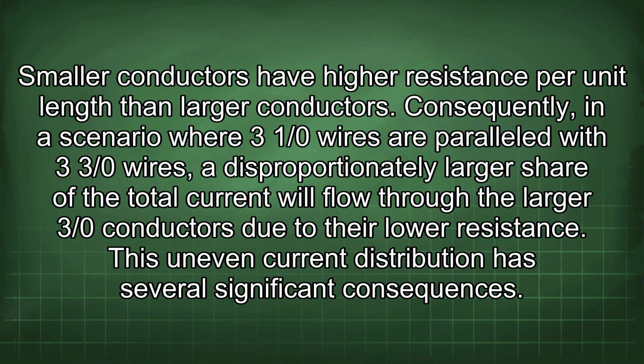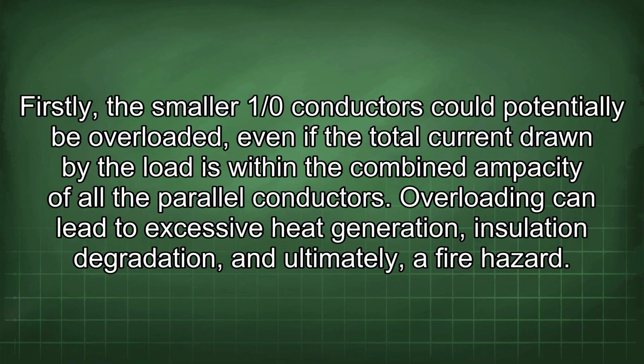Consequently, in a scenario where 3 1/0 wires are paralleled with 3 3/0 wires, a disproportionately larger share of the total current will flow through the larger 3/0 conductors due to their lower resistance. This uneven current distribution has several significant consequences. Firstly, the smaller 1/0 conductors could potentially be overloaded, even if the total current drawn by the load is within the combined ampacity of all the parallel conductors.